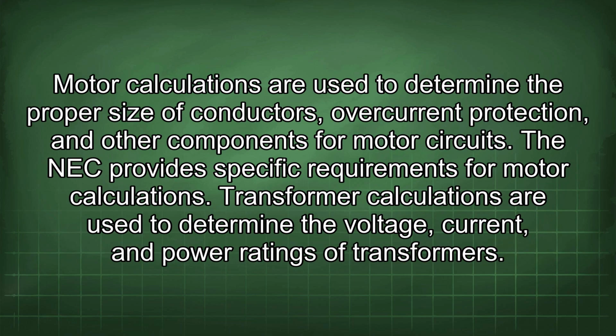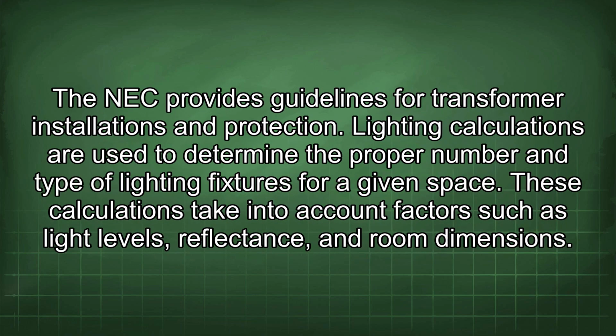Motor calculations are used to determine the proper size of conductors, overcurrent protection, and other components for motor circuits. The NEC provides specific requirements for motor calculations. Transformer calculations are used to determine the voltage, current, and power ratings of transformers. The NEC provides guidelines for transformer installations and protection. Lighting calculations are used to determine the proper number and type of lighting fixtures for a given space. These calculations take into account factors such as light levels, reflectance, and room dimensions.